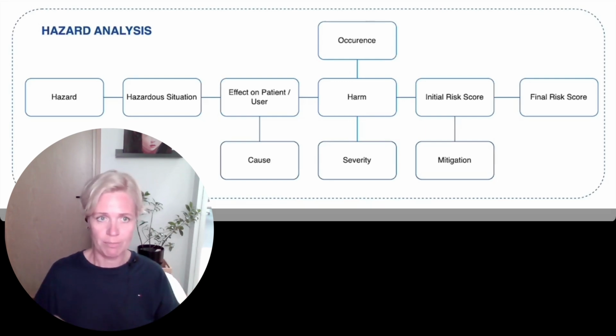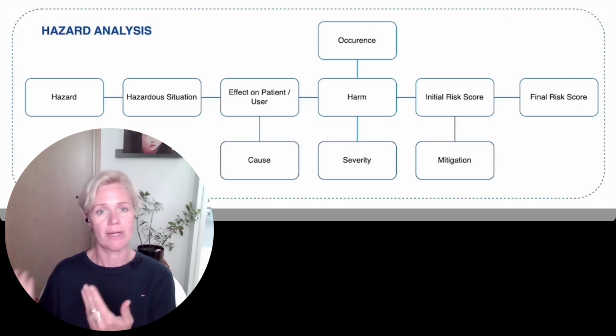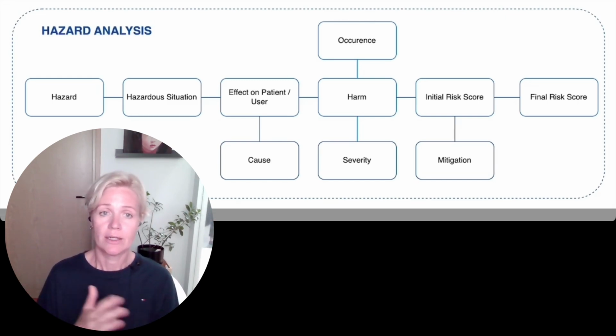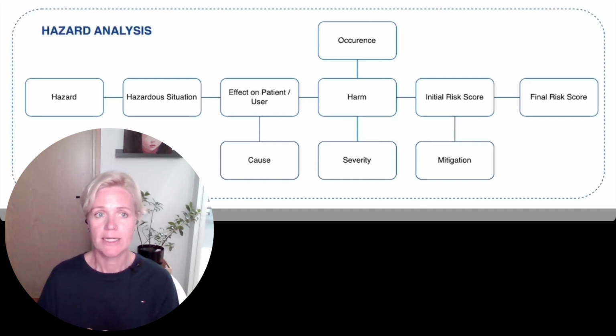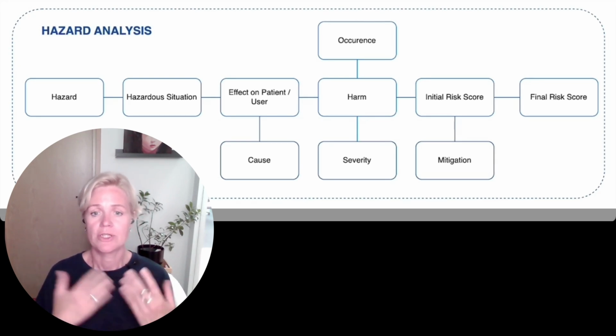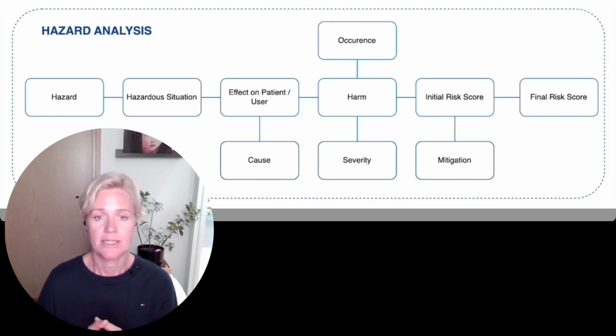So to sum it all up, first you identify the hazards, the potential source of harm, describe the situations where hazards may be realized and the harm that these hazards can cause. If the hazard is on an unacceptable level, you will have to mitigate or control that risk and describe the risk control that mitigates that risk. Next, you will have to put in place the verification actions. These are tests that ensure that the mitigation actions actually mitigate the risk to acceptable level.